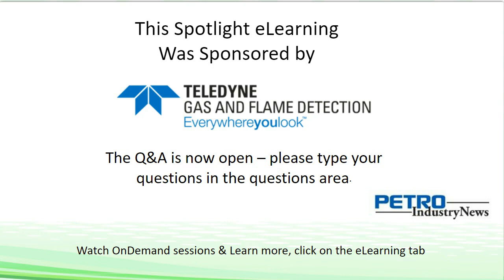Okay, thank you, François. We have another question here. Do all fixed flammable gas detectors have to be EX rated? I see a number of manufacturers offering more general purpose products without an EX rating, but promoted as safe area gas detection, such as boiler rooms. I presume that just depends on the rating of the area, but any comments on that? I answered a similar question earlier. Maybe François would like to give his thoughts on this one.